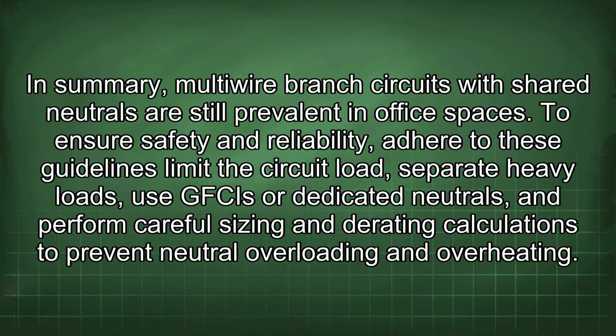In summary, multi-wire branch circuits with shared neutrals are still prevalent in office spaces. To ensure safety and reliability, adhere to these guidelines: limit the circuit load, separate heavy loads, use GFCIs or dedicated neutrals, and perform careful sizing and derating calculations to prevent neutral overloading and overheating.